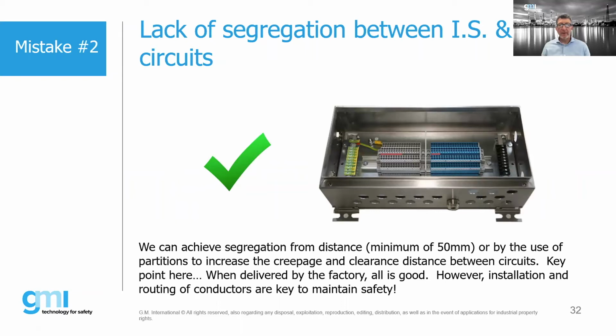Right. Okay. So here's a good example that we show in this panel. Again, we have a separation between IS and non-IS circuits. So that 50 mil could actually be up and over a segregation partition of something like this. It could be free air. Or when we're talking about actually cabling, we can use shielded cables, especially when we're talking about cable runs into trays and things like that, or armored cables.